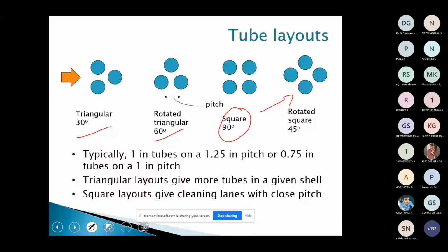Usually, we call it a 1-inch tube on 1 1/4 inch. We call it something like that. 1-inch tube on 1 1/4 means the diameter of the tube will be 1 inch and the pitch distance is 1.25 inches. That is the center distance. So the center distance will be 1.25 inches, of which the tube diameter will be 1 inch. This is the normally used standard size in a shell and tube. And of course, sometimes 0.75 inch on 1 inch pitch. That is, the diameter of the tubes will be 0.75 inches and the pitch distance will be 1 inch.